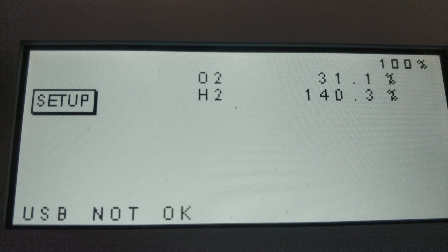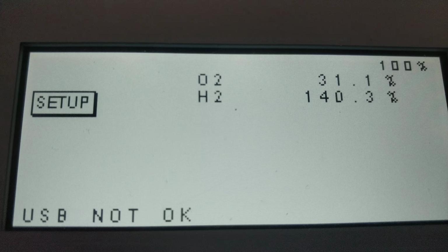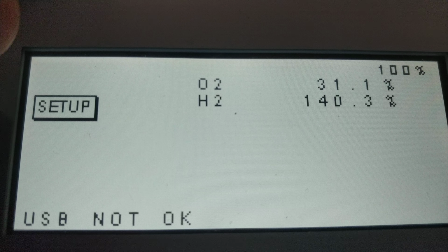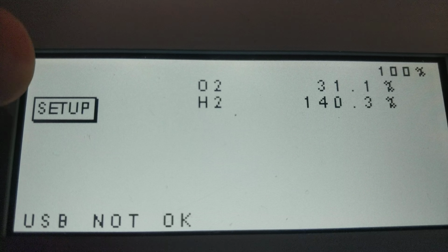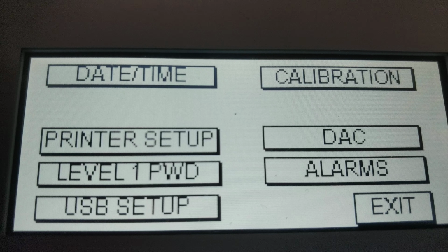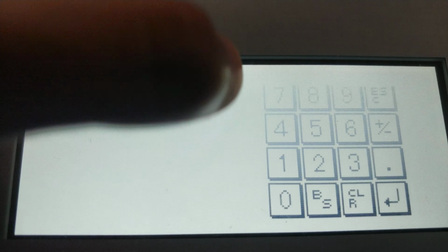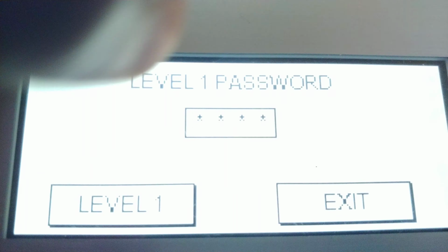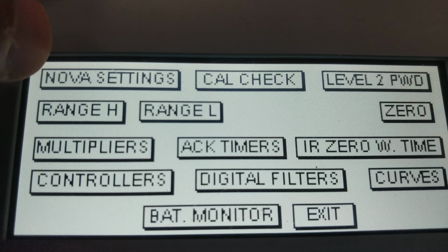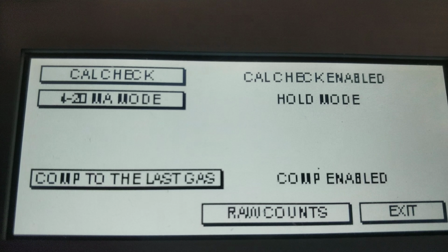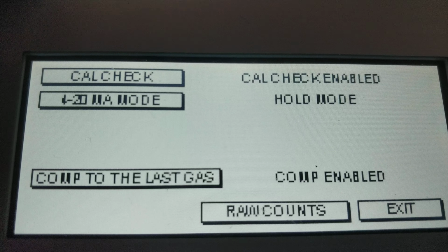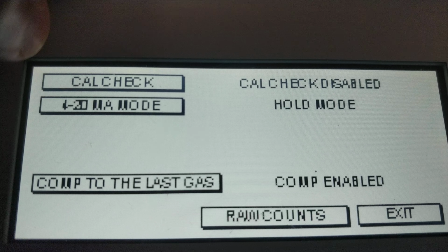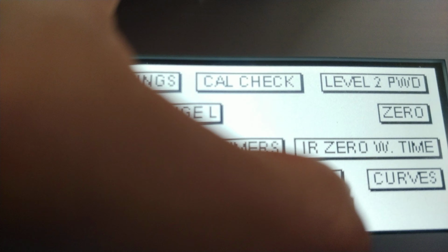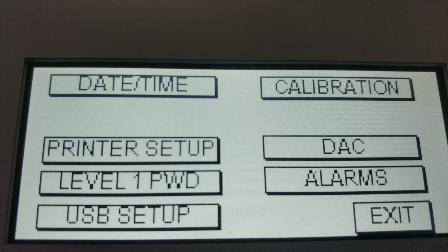So now we want to do one more thing while we're on the screen. We want to disable the calibration check, just to make sure everything goes through without any extra hiccups. So we'll just press setup, and then level 1 password again to level 1. And we go 270 again, so 270, enter, level 1 password, and then Nova settings. So press the Nova settings button. It says CalCheck enabled. For now we just want to disable this. CalCheck disabled, exit, exit. So now we're ready to do a calibration.